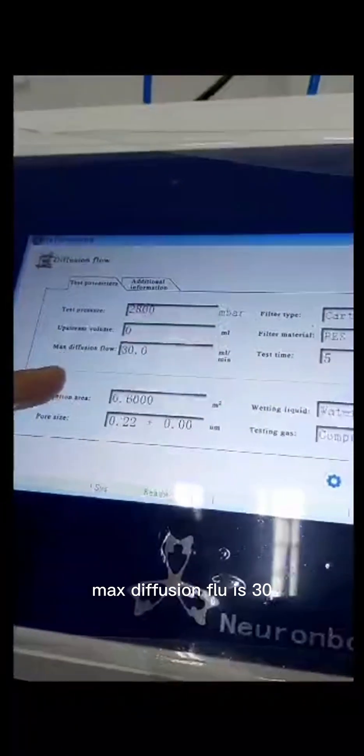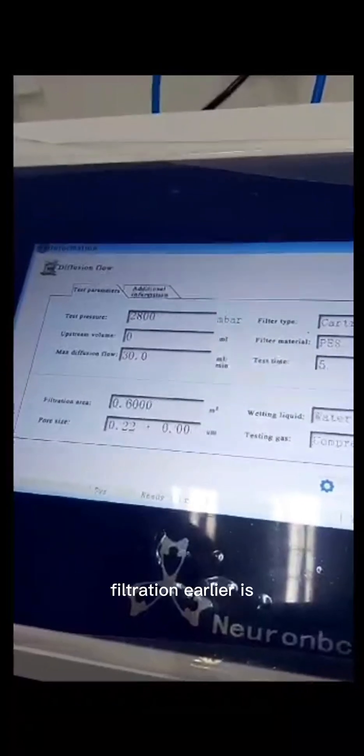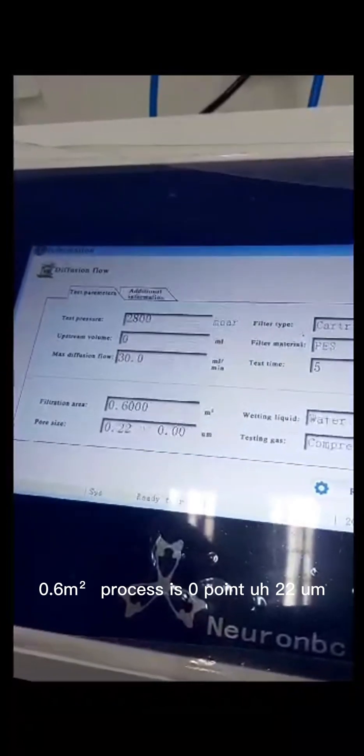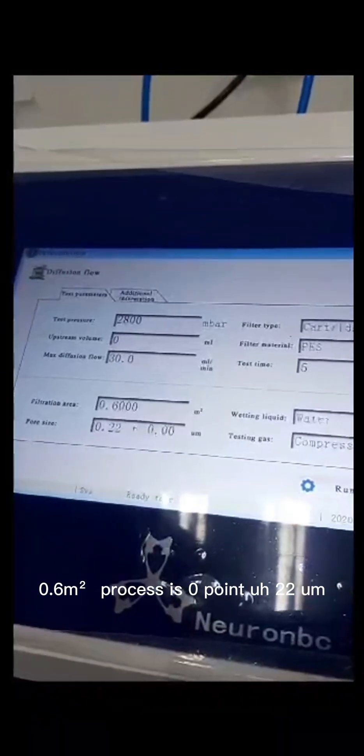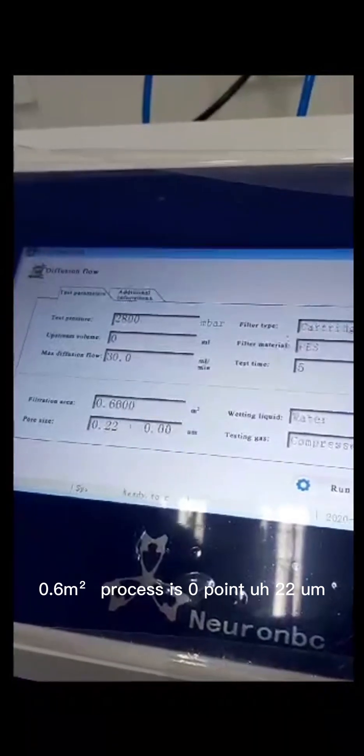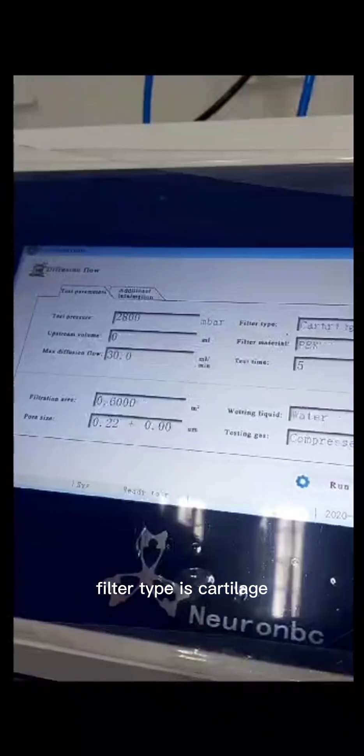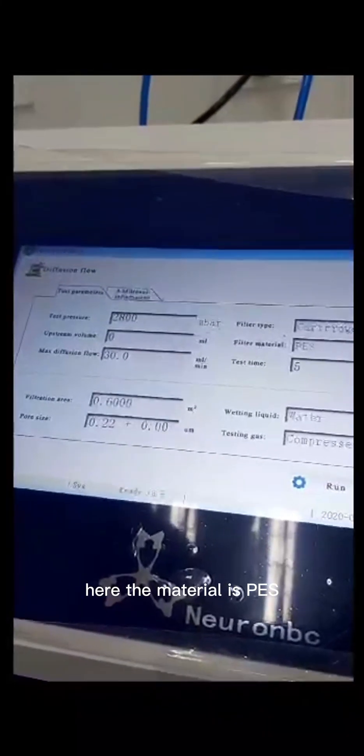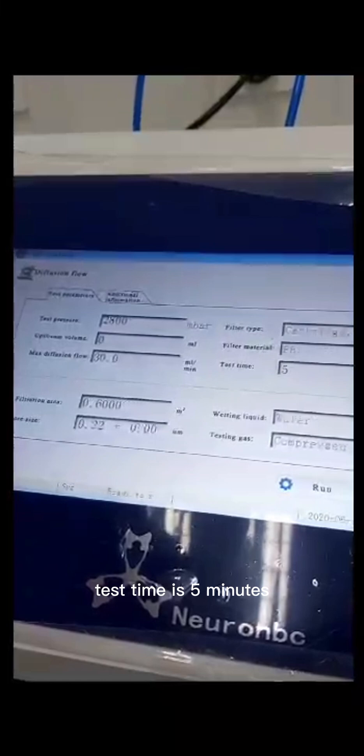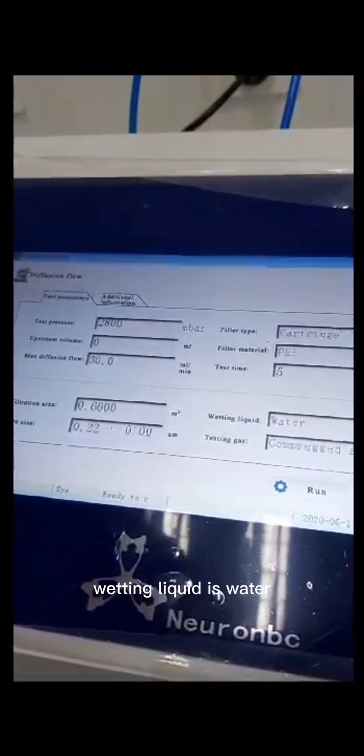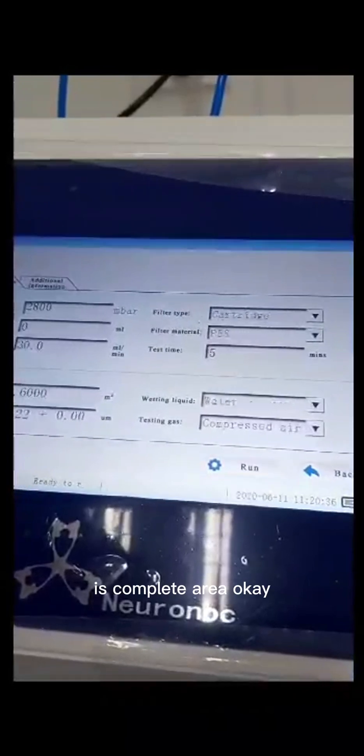Upstream volume. Max diffusion flow is 30 ml per minute. Filtration area is 0.6 square meter. Pore size is 0.22 um. Filter type is cartridge. Filter material is PES. Test time is 5 minutes. Wetting liquid is water. And test gas is compressed air.